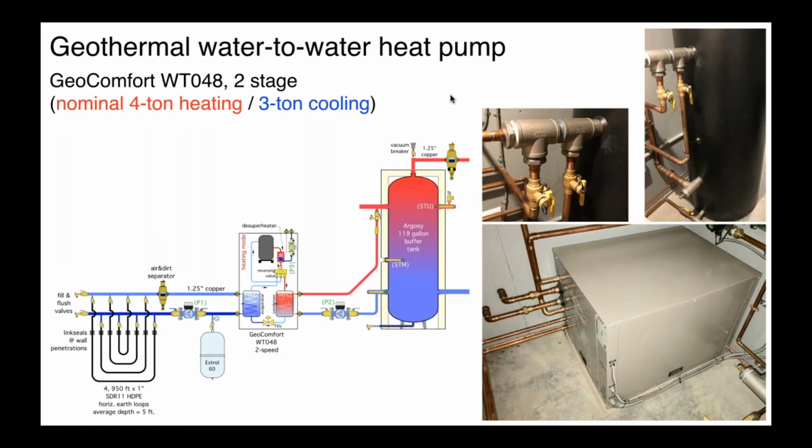In fact, with 2 heat pumps now, we can actually have on the order of about 8 tons. If both heat pumps are running, and we have tested the controls and have been able to confirm this, we can actually have up to 8 tons of heat input going into the system. And what that does is it allows that slab to come up to temperature without literally draining the BTUs out of the rest of the system and causing discomfort in the house.